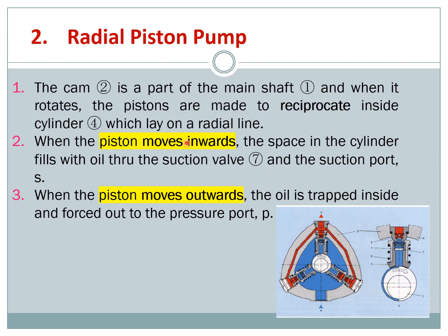The cylinders lie on the radial line. When the piston moves inward, the space in the cylinder fills with oil through the suction valve, so the oil moves inside. When the piston moves outward, oil is trapped inside and forced out at the pressure port P. There are three pistons in this example, so the system can trap and hold that particular oil before sending it out. That is the radial piston pump.